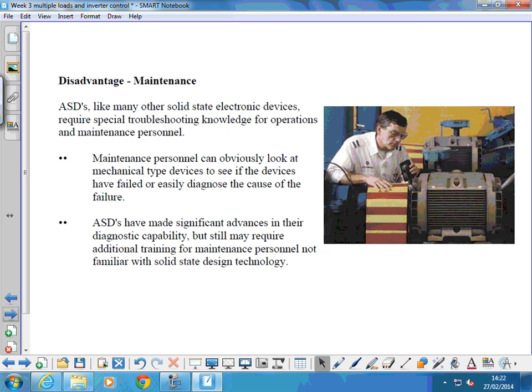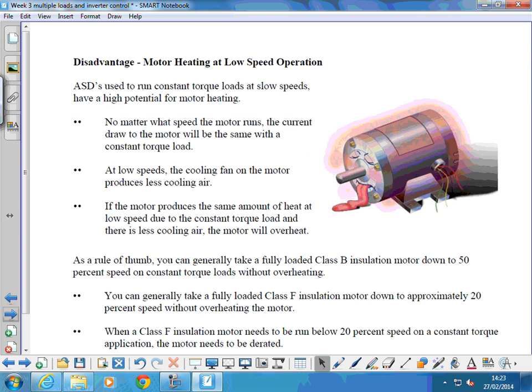Maintenance. Like many other solid-state electronic devices, it requires special troubleshooting knowledge for operations and maintenance personnel. So we're talking about going inside the inverter and finding out what's wrong with it. The average maintenance engineer probably isn't going to have the knowledge or the equipment to be able to do so. So in that case, you're going to want to be carrying complete inverters as spares so that you can swap them over. Yeah, or have a bypass solution. Yeah. They do have a lot of diagnostic capability, but again, that could require additional training to be able to understand that. And in my experience, the manuals for these things are like trying to read the Bible. They're not always particularly user-friendly, as it were.